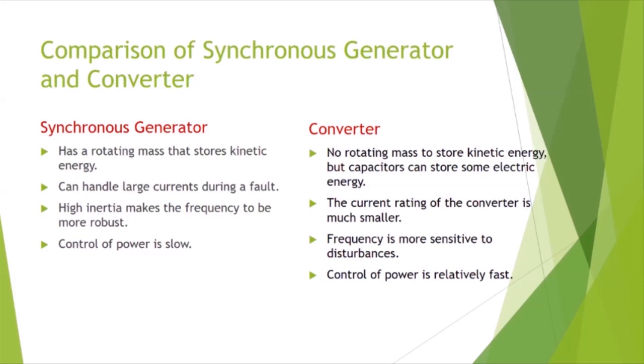Another advantage of synchronous generator is it can handle large currents during a fault. For a short period, it can handle large currents. And high inertia makes frequency to be more robust because with small change in speed, it can release or absorb energy because of the large inertia. On the other hand, control of power is slow because power is generated using turbines, steam turbines or hydro turbines, and there are time constants associated with the control of those turbines.